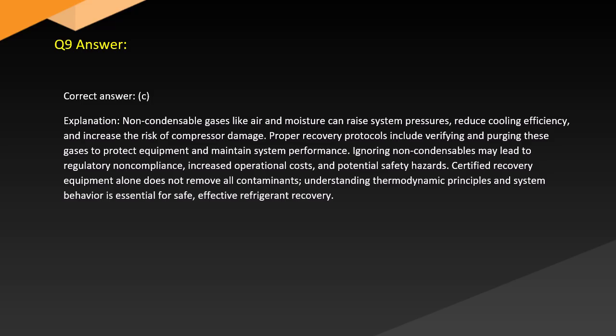Answer. Correct answer. C. Explanation. Non-condensable gases like air and moisture can raise system pressures, reduce cooling efficiency, and increase the risk of compressor damage. Proper recovery protocols include verifying and purging these gases to protect equipment and maintain system performance. Ignoring non-condensables may lead to regulatory non-compliance, increased operational costs, and potential safety hazards. Certified recovery equipment does not remove all contaminants. Understanding thermodynamic principles and system behavior is essential for safe, effective refrigerant recovery.